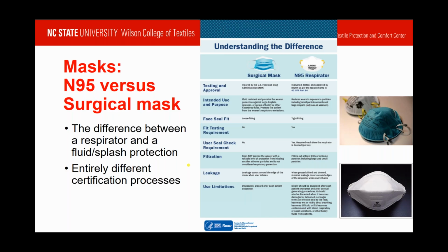N95 respirators, as they need to provide respiratory protection, are tested for face seal, fit, and have fit testing requirements. The user needs to perform a seal check prior to using it. It's not just about filtration of the fabric or the base material, but also about how the entire product fits the nose, face, and mouth and closes it up from the environment to have an effective seal, because that has been shown to be the biggest problem for good quality filtration fabric to provide any type of protection to users.